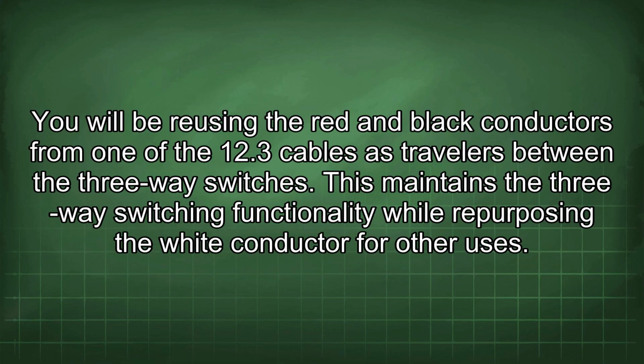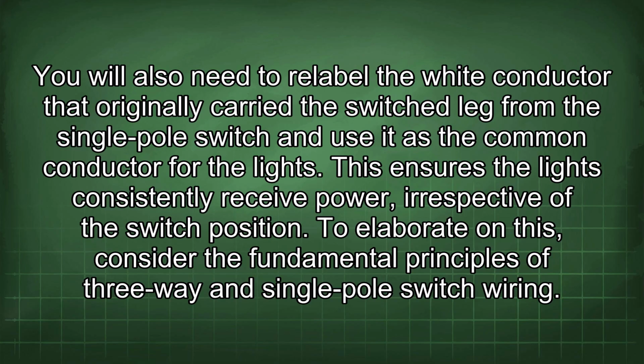You will be reusing the red and black conductors from one of the 12.3 cables as travelers between the three-way switches. This maintains the three-way switching functionality while repurposing the white conductor for other uses. You will also need to relabel the white conductor that originally carried the switched leg from the single-pole switch and use it as the common conductor for the lights. This ensures the lights consistently receive power, irrespective of the switch position.